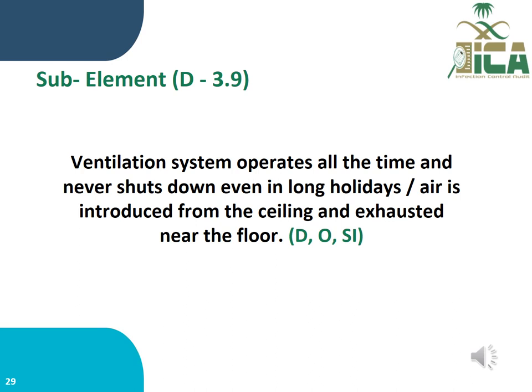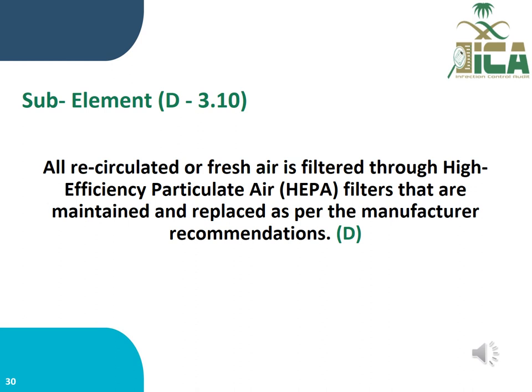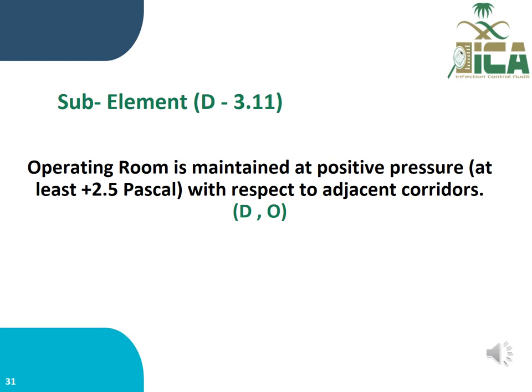Sub-element D3.9: The ventilation system operates at all times and is never shut down, even during long holidays. Air is introduced from the ceiling and exhausted near the floor. Sub-element D3.11: The operating room is maintained at positive pressure of at least 2.5 Pa with respect to adjacent corridors. This is done by documentation and observation.